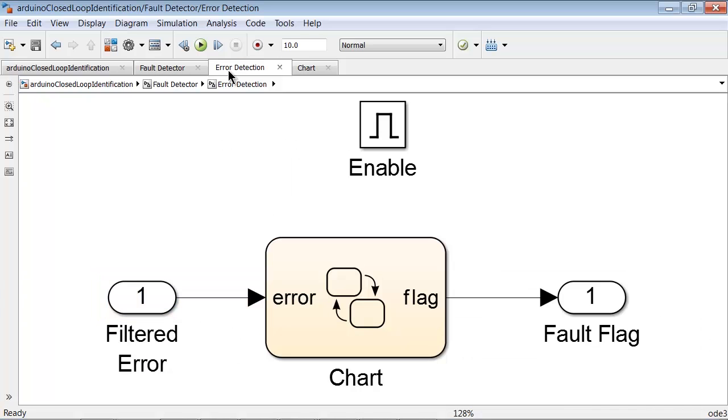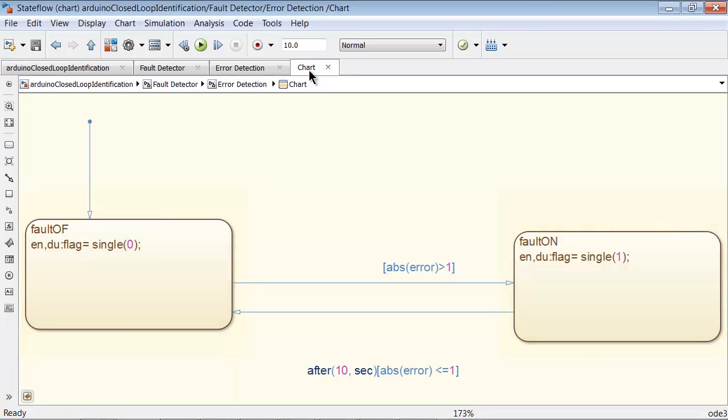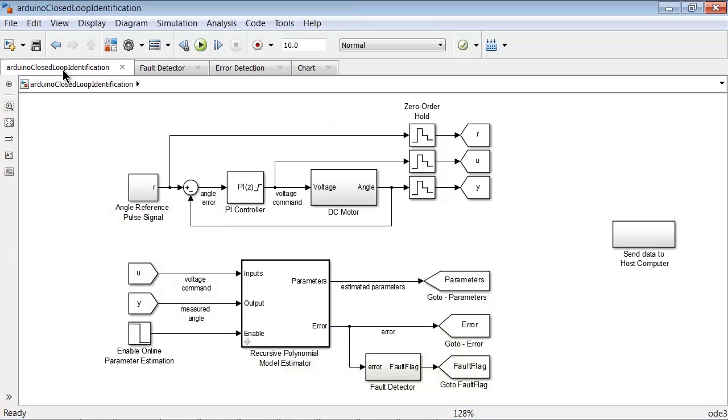This filtered signal is the input to the fault detection algorithm which is implemented using a simple two-state state flow chart. The state flow chart sets the fault flag to 1 when the filtered error is greater than a threshold and resets the fault flag back to 0 after the filtered error is less than the threshold for 10 seconds.